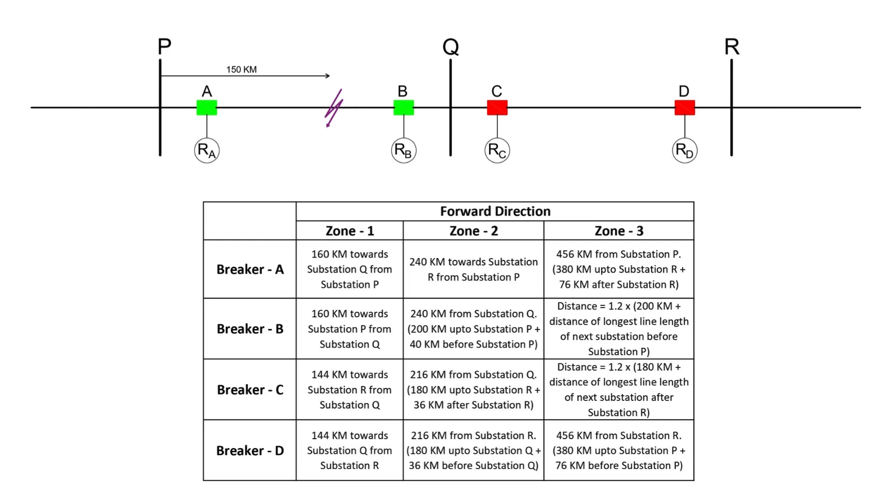But what if one of the breakers, let's say breaker A, fails to trip? In that case, the relay at substation Q will immediately send a direct trip signal via PLCC to substation P to trip breaker A and isolate the faulty line from both ends. The relay B will sense the fault in zone 1 because the distance of the fault from Q is 50 kilometers, which is within the zone 1 limit of B.